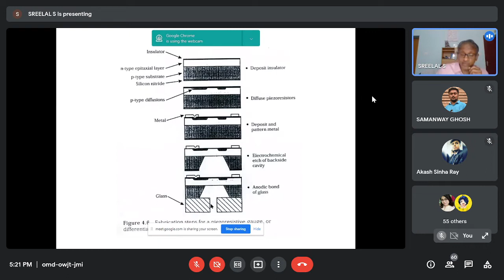When pressure is applied, the diaphragm will deflect. The deflection or strain on the diaphragm leads to a resistance change due to the piezoresistive property of the resistive devices deposited from the substrate. This is how the pressure transducer basically works. This cross-sectional view shows the pressure port on the back side, the etched cavity, the silicon diaphragm, a p-type diffused piezoresistor, and metal conductors.